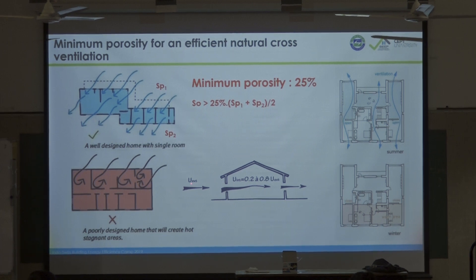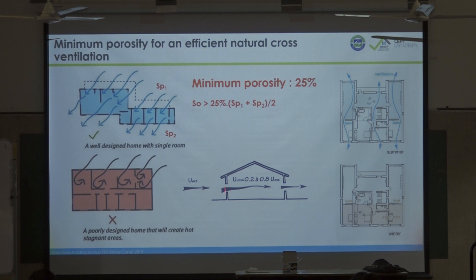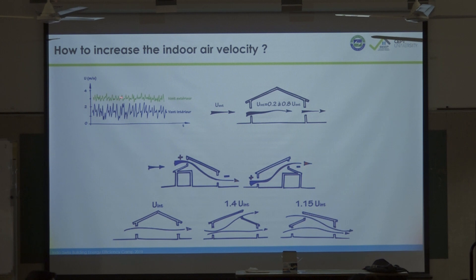If you have for instance an air velocity of 3 meters per second outside, keep in mind that inside you'll get only 20 to 80 percent of that, depending on porosity, size of openings, etc. So your wind potential with coefficients k1 and k2 will give you an idea of the air velocity you can get inside.